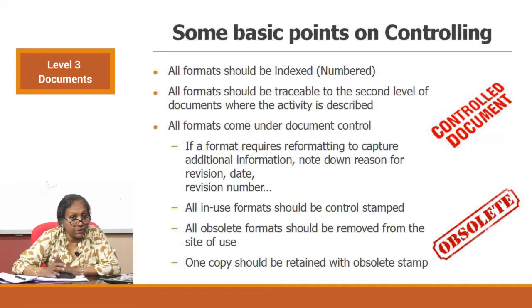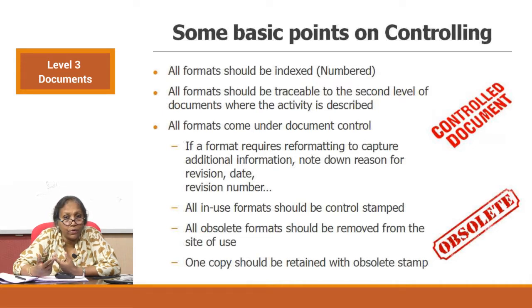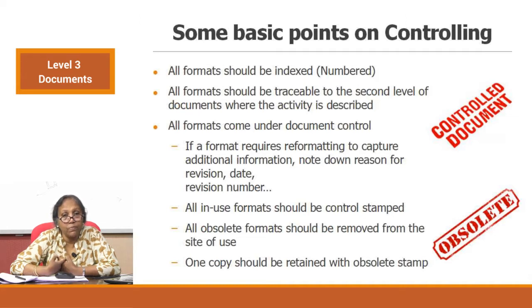Formats come under document control. If a format requires reformatting to capture additional information, note down the reason for revision and the revision number — we will discuss all these details. All in-use formats should be control-stamped — very important. Obsolete formats should be removed from the site of use, and one copy of the obsolete format should be kept for reference, stamped with the obsolete stamp. Why? Because at some point later you would want to know why you made that amendment, why you obsoleted it, and what area of the activity it was not capturing or why it was too complicated for the technician to fill in.